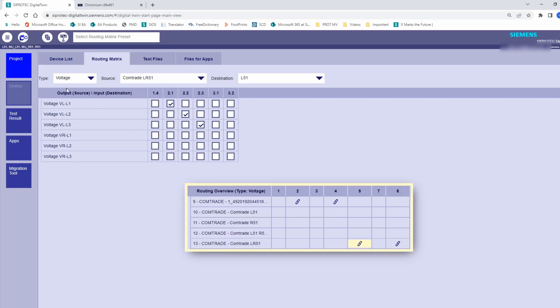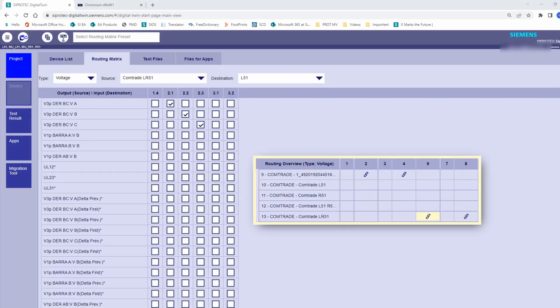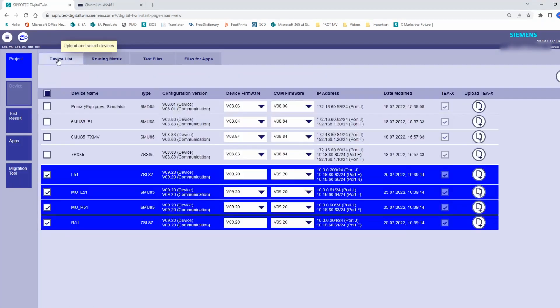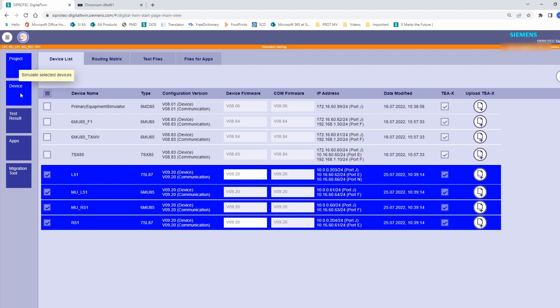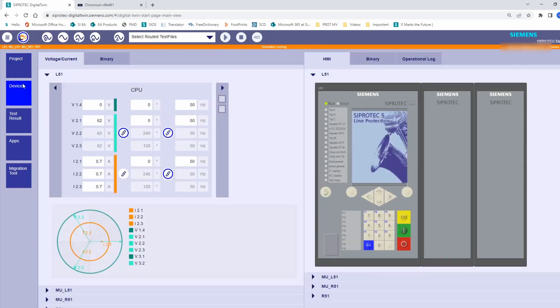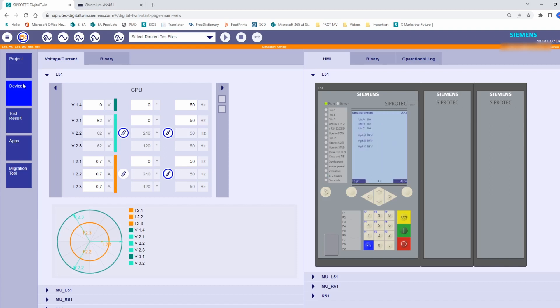Now the preparation is ready, and we can start our simulation. In this application, we are going to test the GOOSE messages as well. We have the position of the circuit breakers and disconnectors being acquired by the merging units, and they are transmitted via GOOSE to the devices. And we have also the trips being released by the protection device and transmitted to the merging units.